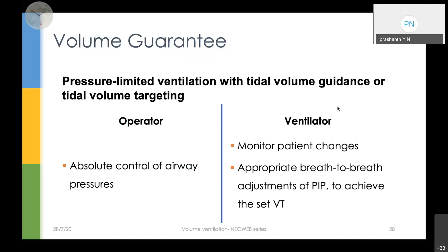Another definition: in volume guarantee or tidal volume targeted ventilation, we're just modifying the pressure control ventilation, where we target how much tidal volume will go into the baby by microprocessor directed adjustments of inflation pressure, that is PIP, and inflation time. Here the intelligence is in the microprocessor. We are using the tidal volumes which are expired by the baby, not inspired by the baby.